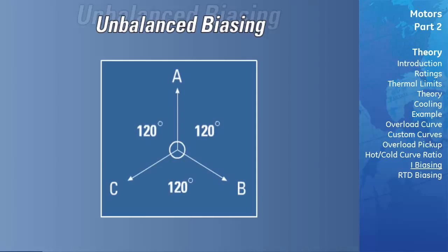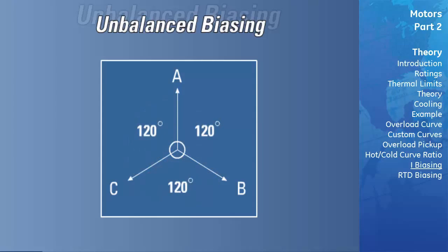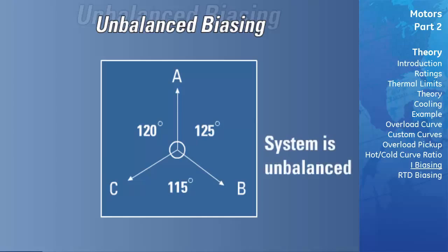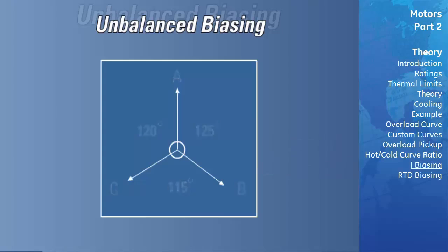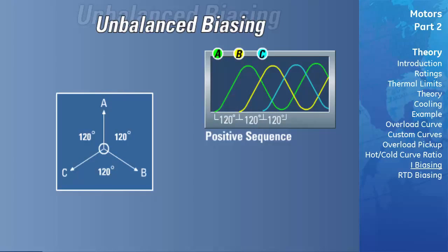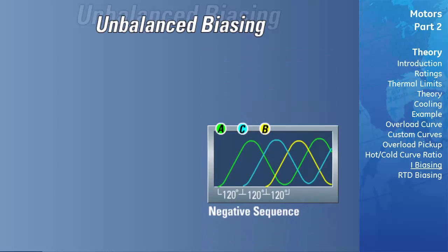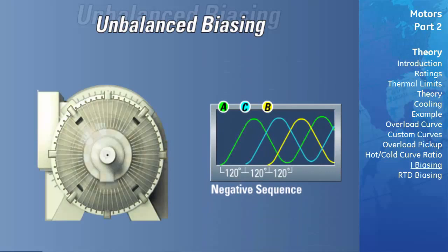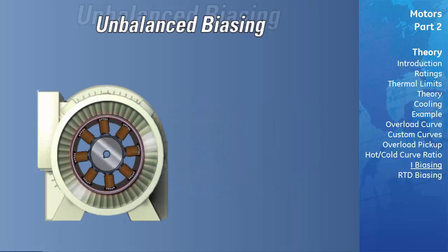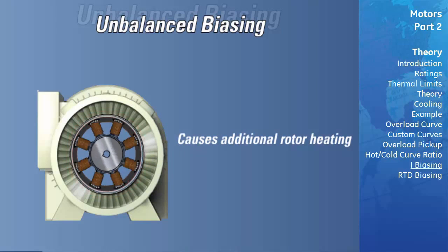A balanced three-phase system is one in which the phase vectors are 120 degrees apart and of equal magnitude. If either condition is not met, the system is considered unbalanced. The amount of unbalance is calculated by comparing the positive sequence current to the negative sequence current. A positive sequence set consists of three equal vectors displaced by 120 degrees with phase sequence A, B, C. A negative sequence set has phase sequence A, C, B. Negative sequence currents — or unbalanced phase currents — will cause additional rotor heating that will not be accounted for by electromechanical relays and may not be accounted for in some electronic protective relays.